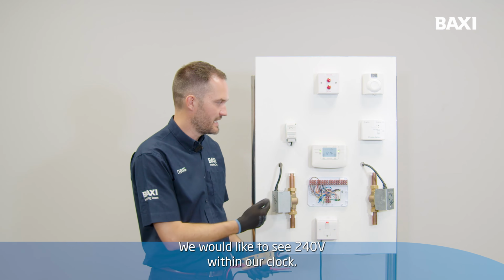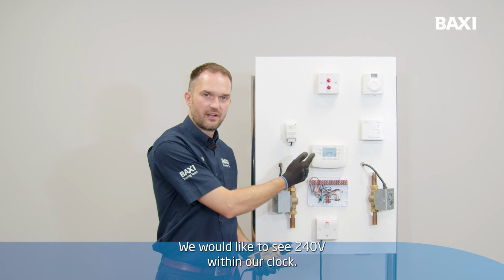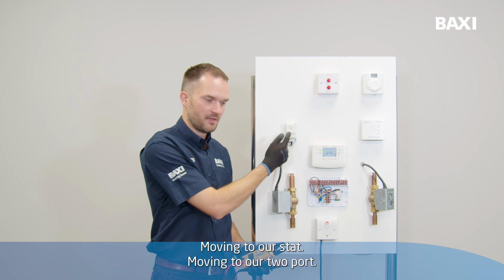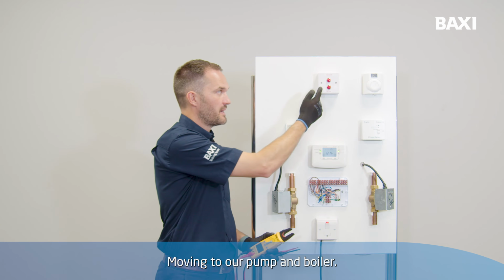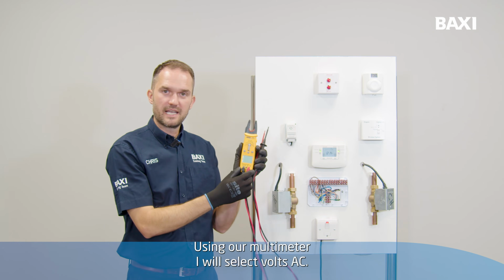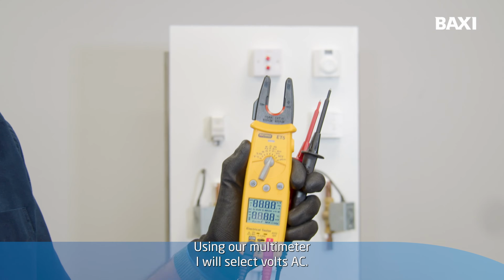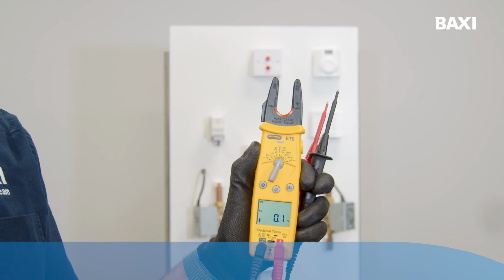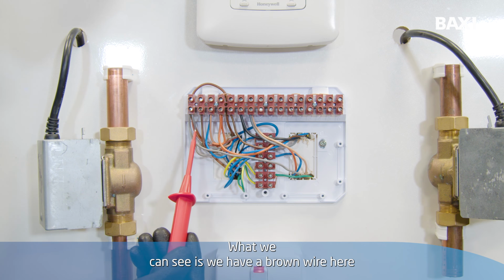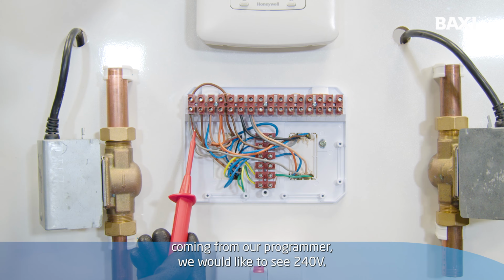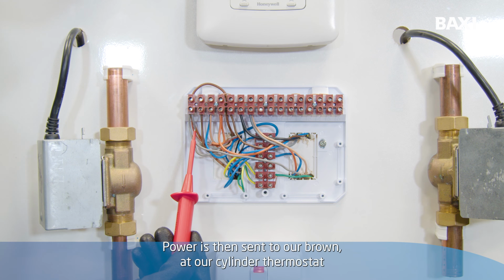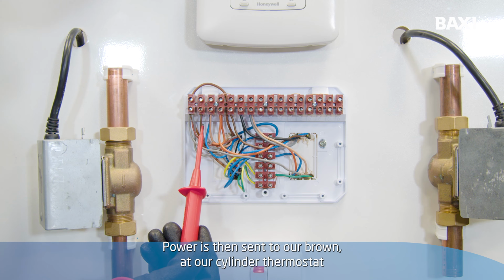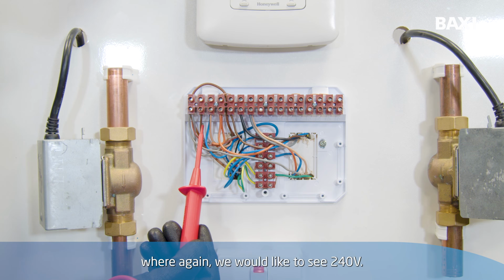We would like to see 240 volts within our clock, move into our stat, move into our 2-port, move into our pump and boiler. Using our multimeter, I will select volts AC. What we can see is we have a brown wire here coming from our programmer. We would like to see 240 volts. Power is then sent to our brown at our cylinder thermostat, where again we would like to see 240 volts.